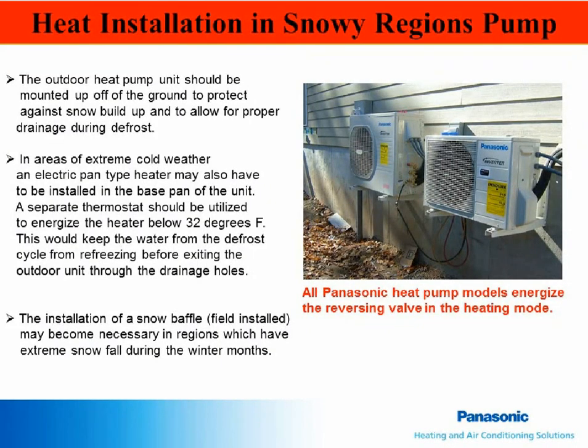In snowy areas, heat pump outdoor units should be elevated to keep snow from blocking airflow and to allow for proper draining during defrost. In some cases, heat tape or a pan heater may need to be installed in the bottom of the unit to keep defrost water from refreezing and to allow drainage from the unit.